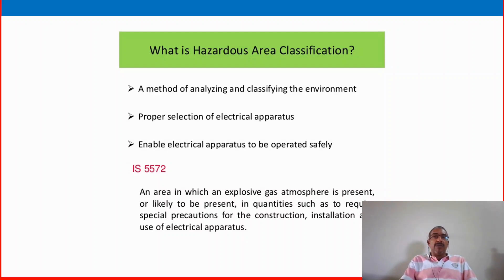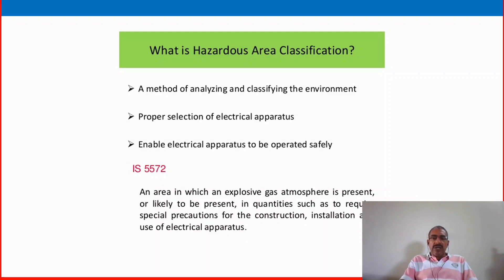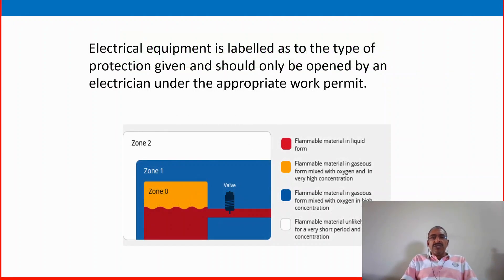We can define which type of tools we can use in that area, and we can add in permits that the area is classified in various zones, to enable electrical apparatus to be operated safely — per IS 5572. An area in which an explosive gas atmosphere is present or likely to be present in quantities such as to require special precautions for the construction, installation and use of electrical apparatus. Electrical equipment is labeled as to the type of protection given and should only be opened by an electrician under the appropriate work permit. There is a picture showing various zones — Zone 0, Zone 1, and Zone 2.